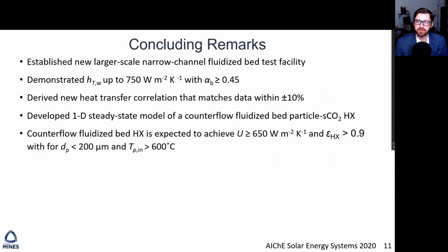In conclusion, we have established a new test facility for investigating the impact of bed operation and particle properties on heat transfer and fluidization in a narrow channel fluidized bed. We have demonstrated particle-to-wall heat transfer up to 750 watts per meter squared Kelvin with particle volume fractions greater than 0.45. From our experimental data, we derived a new heat transfer correlation that matched our data within plus or minus 10%. We developed a steady-state one-dimensional model of the heat exchanger, and using that model project overall heat transfer coefficients greater than 650 watts per meter squared Kelvin, more than twice that generally observed with moving packed bed designs, with heat recovery effectivenesses greater than 90% when using particle diameters smaller than 200 microns and inlet temperatures above 600 C.